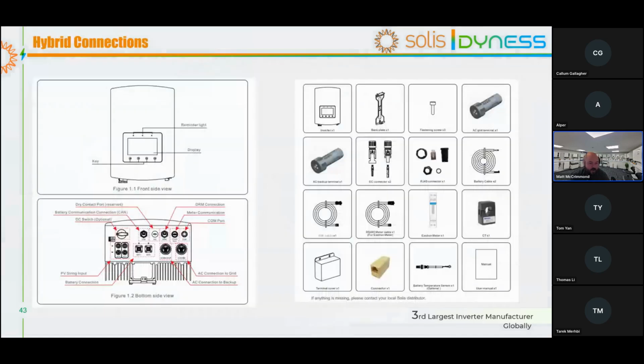So where I want to start off is the actual unit itself, and what you get in the box effectively. So at Solis, we've tried to make it as plug and play as possible. If you look at the bottom of our inverter, it is literally just plugging ports in. What we have is our PV input, of course, our MPPTs, and we have the DC isolator on the unit, so you have an integrated DC isolator. We've got our battery connections, which is where you would connect your Dyness battery in, as shown.